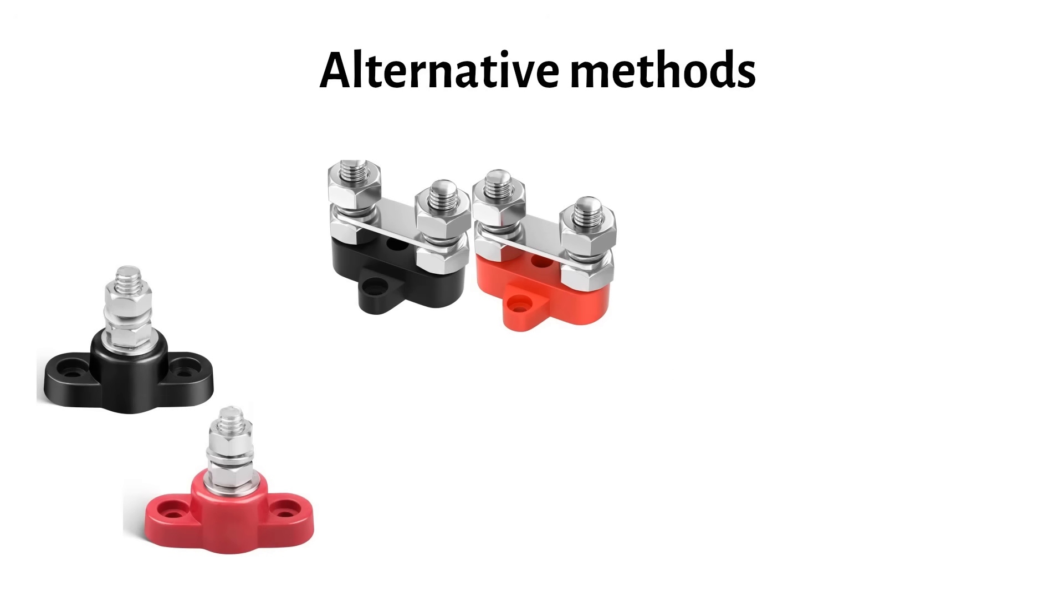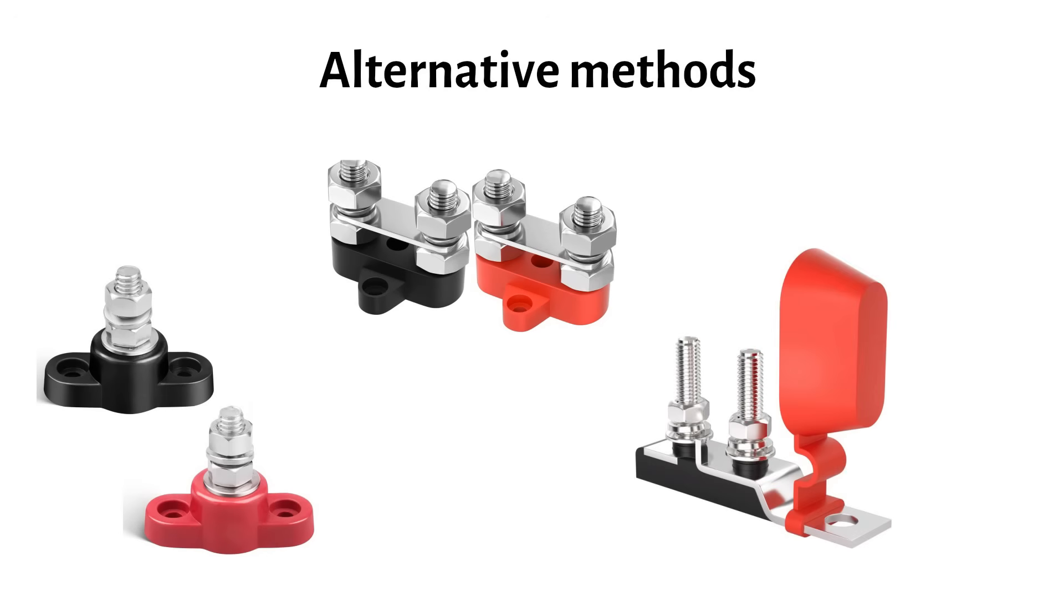There is also a dual MRBF option where one terminal connects to your inverter and another to your charge controller. One thing to keep in mind is that most MRBF terminal blocks have M10 holes, but some M8 versions exist, which is a better fit for the standard M8 battery posts.